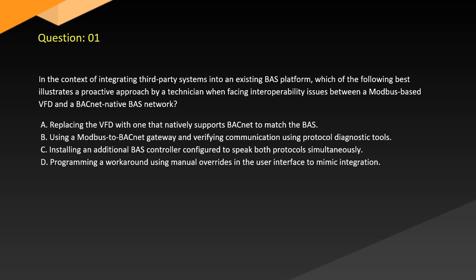Question 1. In the context of integrating third-party systems into an existing BAS platform, which of the following best illustrates a proactive approach by a technician when facing interoperability issues between a Modbus-based VFD and a BACnet-native BAS network? A. Replacing the VFD with one that natively supports BACnet to match the BAS. B. Using a Modbus to BACnet gateway and verifying communication using protocol diagnostic tools.